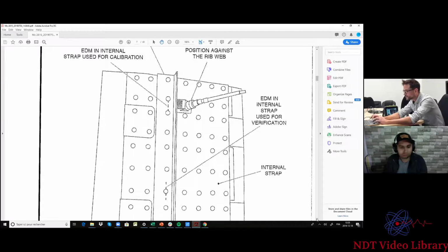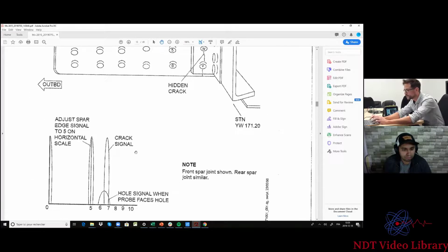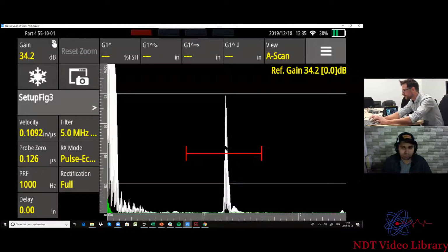Exactly. So if you keep reading the procedure, you have an EDM notch here on the calibration block. On the calibration sample, you should have a signal of about 80% height, and when I come back here, basically I have the exact signal that is expected when I'm doing my sensitivity calibration on my calibration block. So this removes uncertainty from the inspector, making sure the notch is at the proper place and at the proper height with the proper gain.